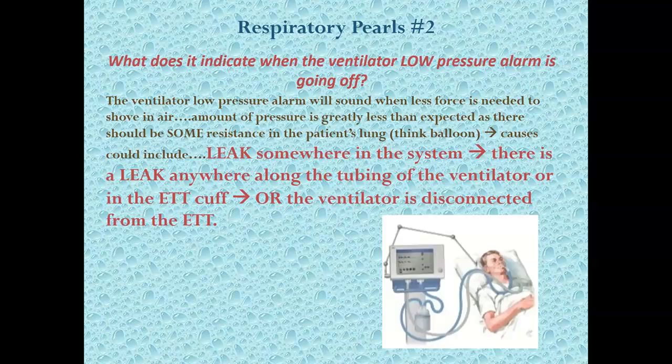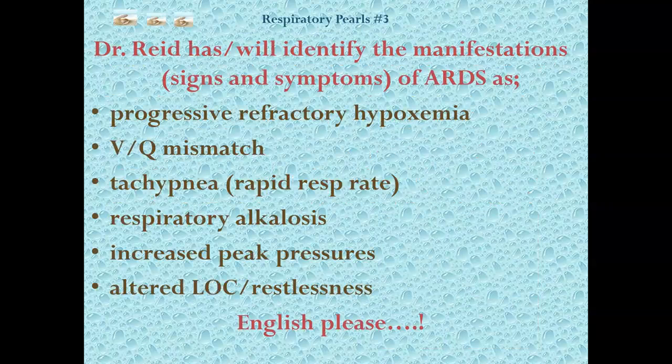But regardless of the reason, if the endotracheal tube balloon is deflated, then there will be air that's blown in and it'll blow out the patient's mouth, and you'll hear it every time the ventilator pushes air in, it blows out. And so sometimes the alarm can go off for that too. Again, high pressure alarm, there's some kind of resistance. Low pressure alarm, there's some kind of leak within the system.